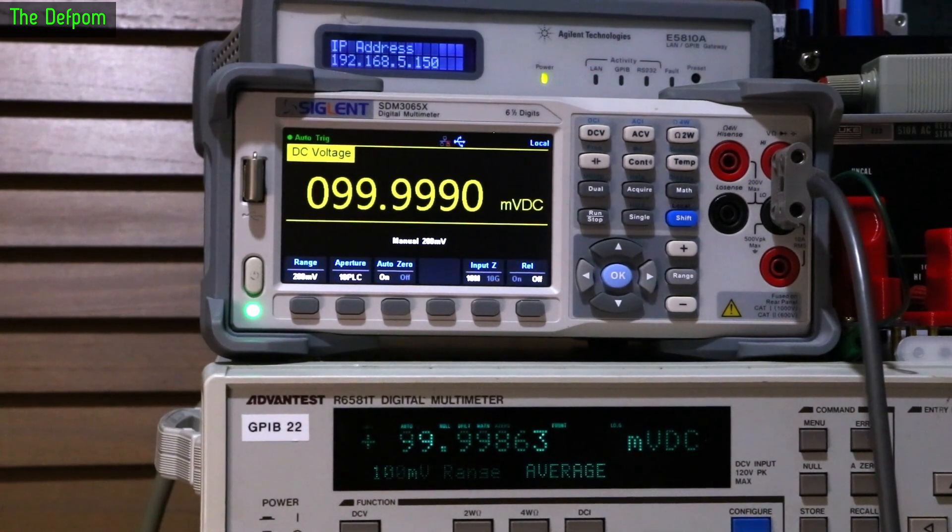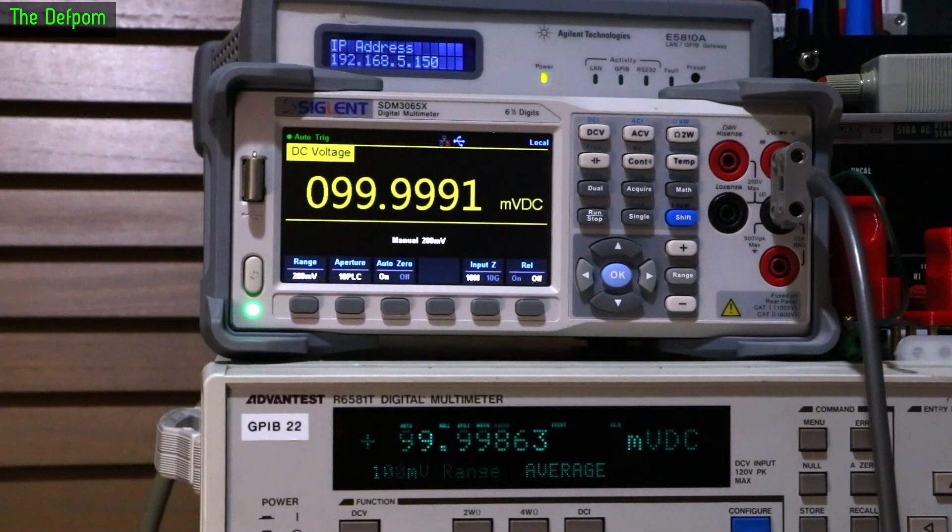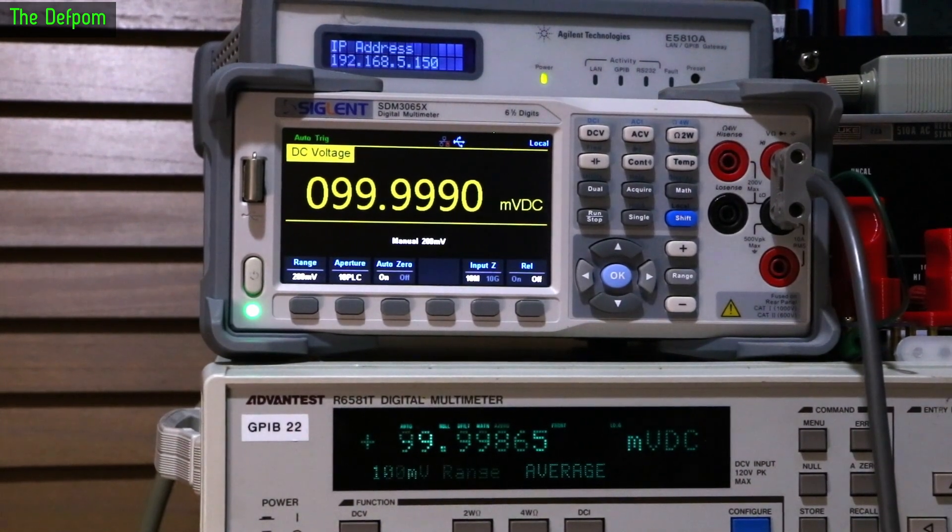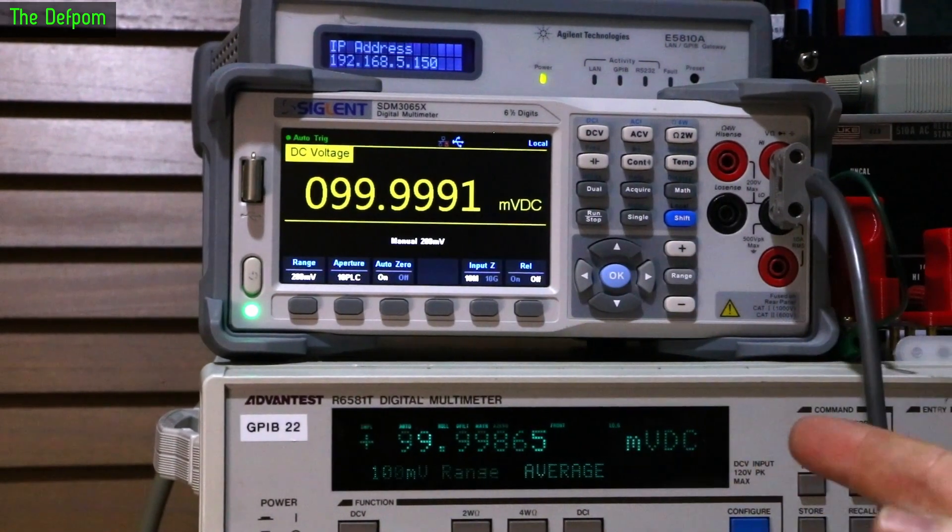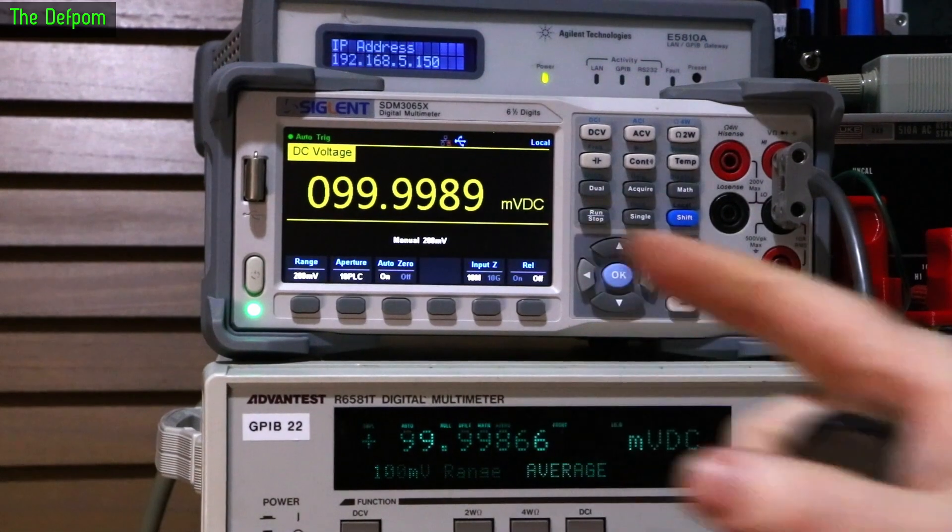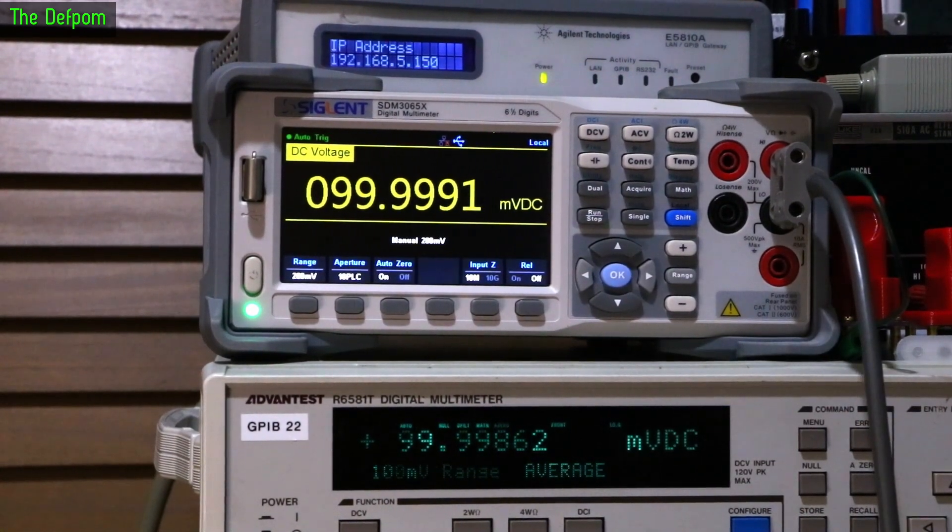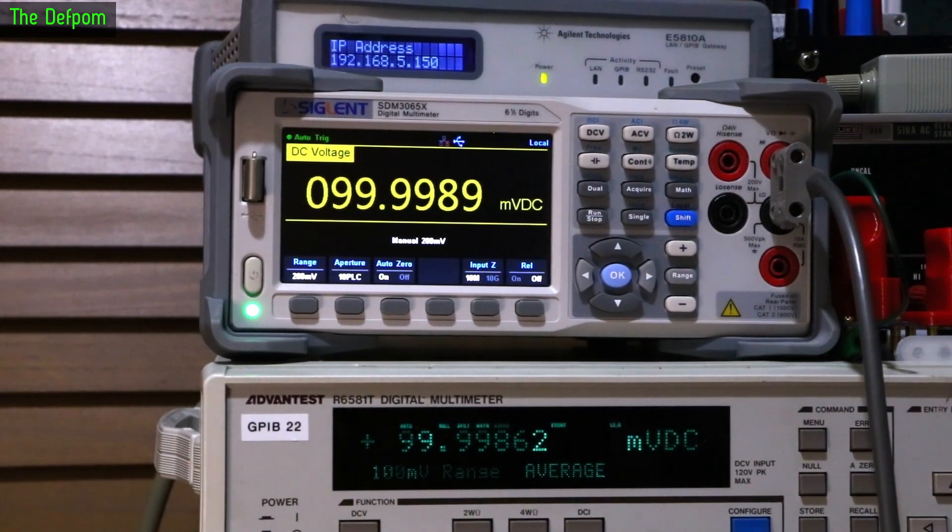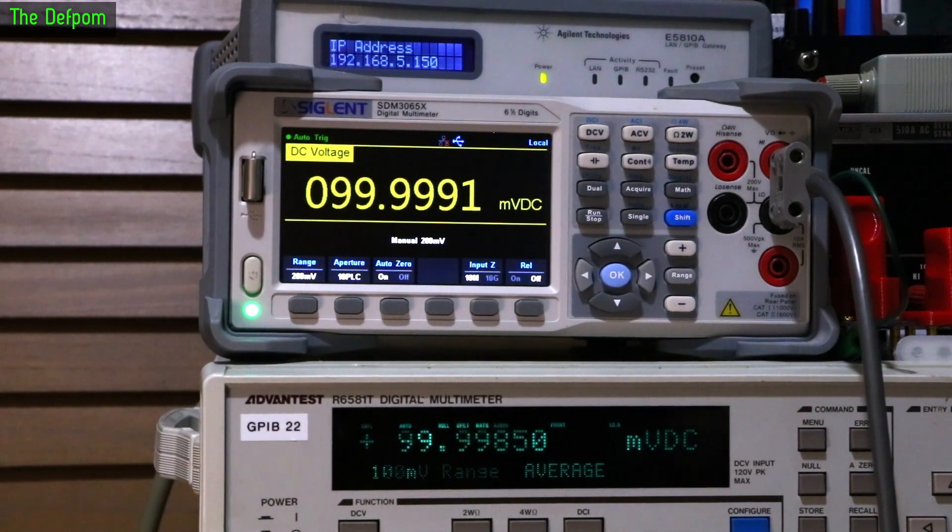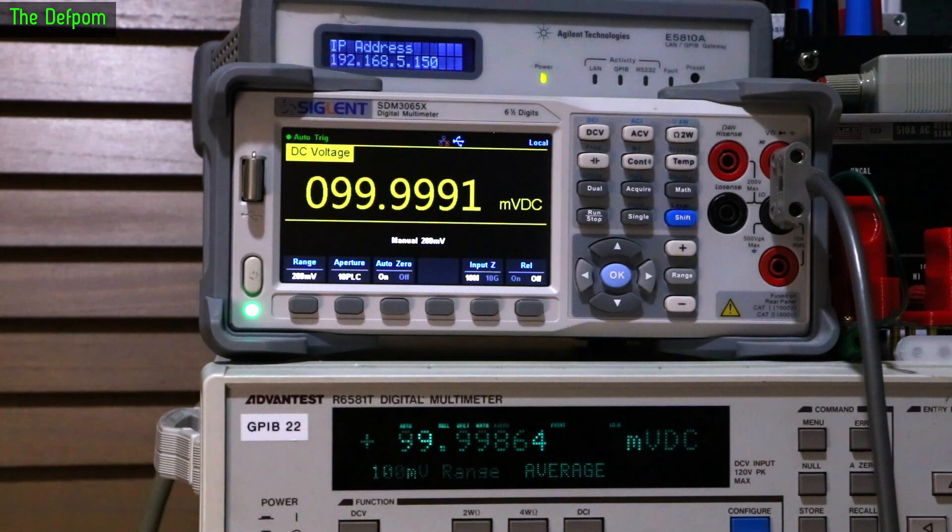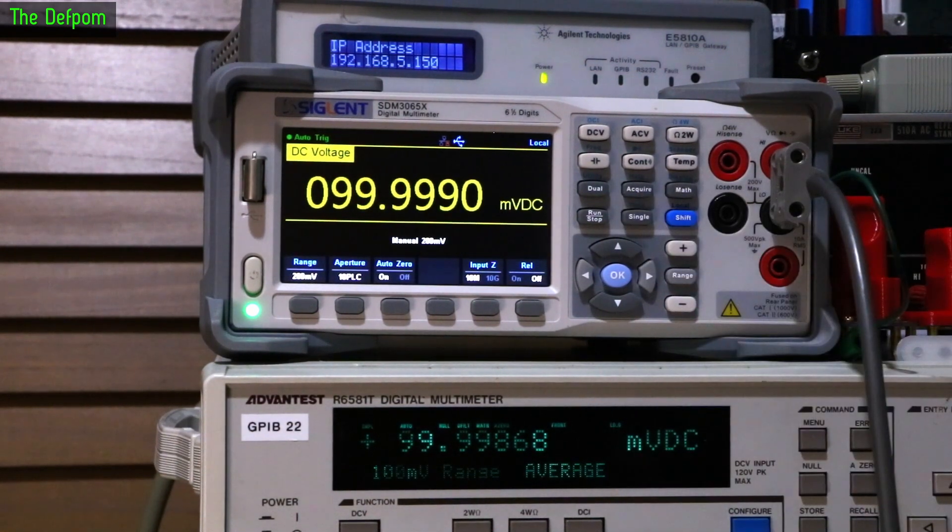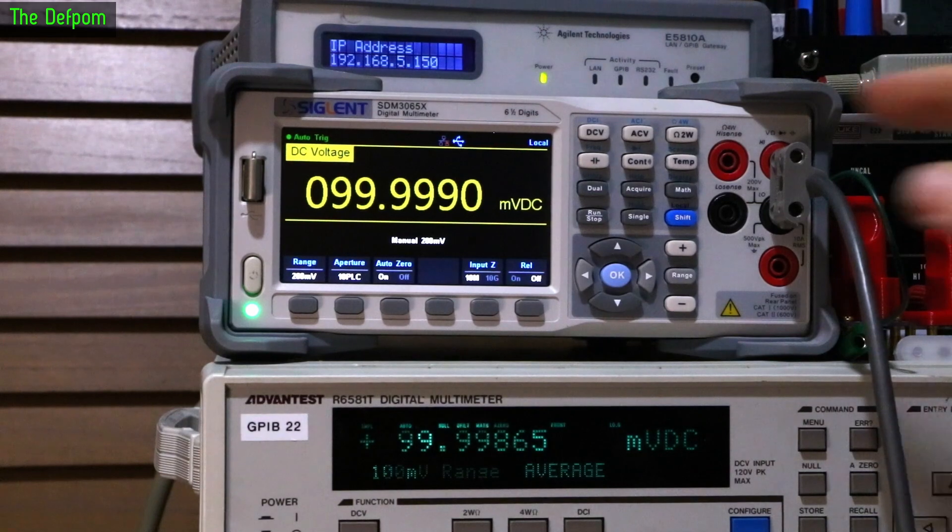The thing to consider about this - because I do have a bit of electrical noise here - as it's reading the values when you're doing a calibration step, it shows the reading you're seeing. If you happen to push save at that point where it's got a little bit of noise coming through, it may offset it very slightly. This one's looking close, something like five counts out, which isn't too bad. But if you really wanted to fiddle with this, you could probably get it better. I've got lots of noise around here. There is no guarding on this thing.